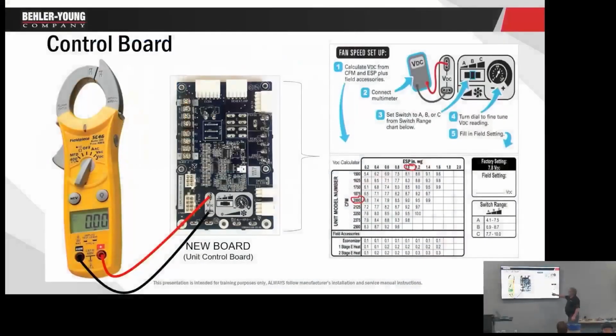I get 0.1 for the economizer. I just took that from here. So my total is 1 inch of static. Everybody see how I got it? So 1 inch from here, 2,000 CFM, 9 volts DC.